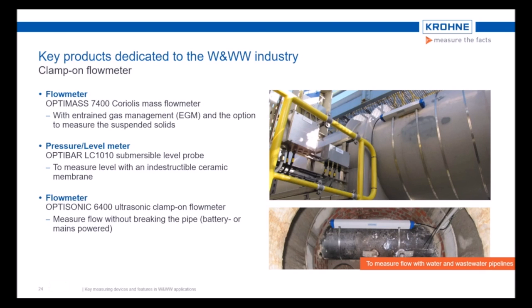In cases or applications where it is not possible or even not cost-effective to break the pipeline to install an inline flow measuring device, operators can make use of this alternative ultrasonic clamp-on flow meter, which can be used for water and even for wastewater pipelines. The unique feature here is that this device can come as an auxiliary powered version or even as a battery operated version to be independent of power within the field.